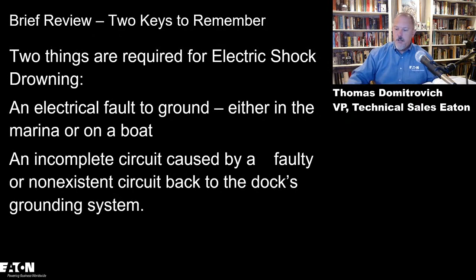So you need two things for an electric shock drowning: you need a fault to ground, and you need an exposed conductor or some exposed wire in the water that is leaking current into the water. That current flows through the water trying to find its way back to the source, and unfortunately it can go through whoever's swimming in that area.